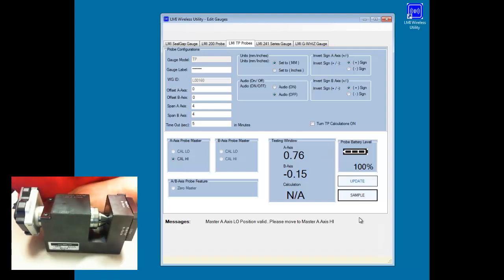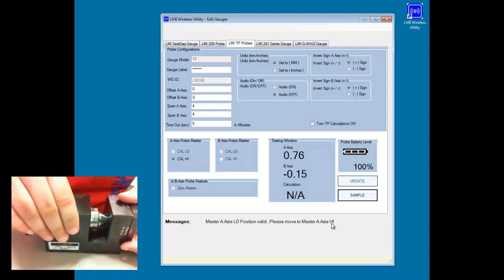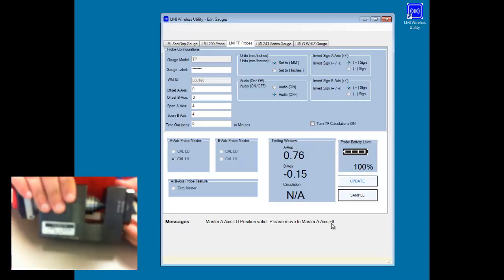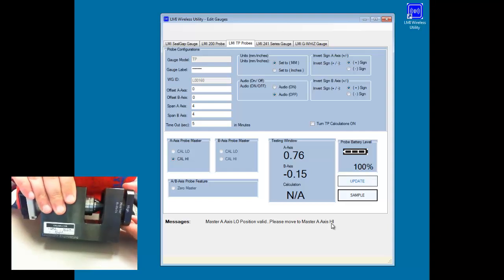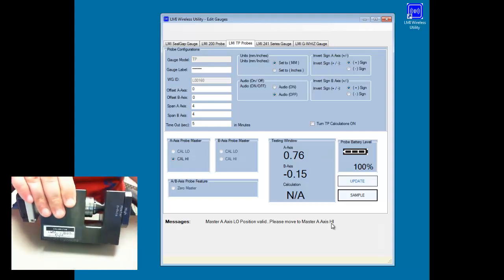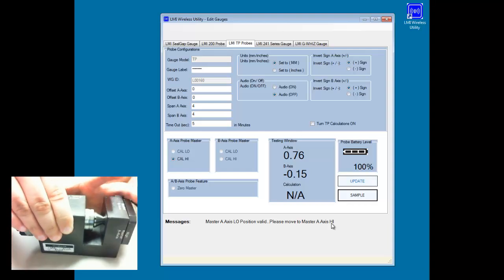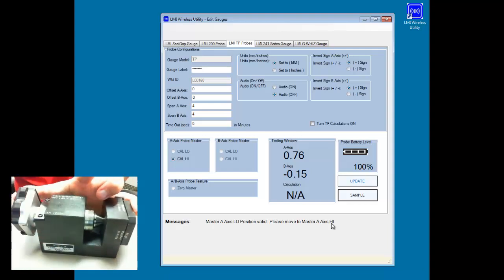It's then telling me that I need to move the master A axis to the high position. So I'll take a look at this. I'm going to pull the end pin out and I will rotate this to high. So high master A axis. I'm then going to hold the gauge in tight, hit the sample button. And then I should be able to do the B axis calibration now.